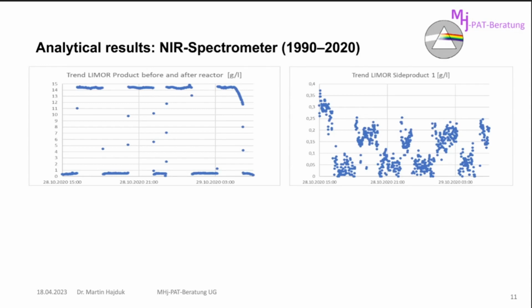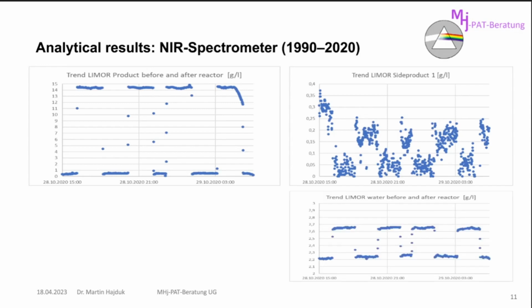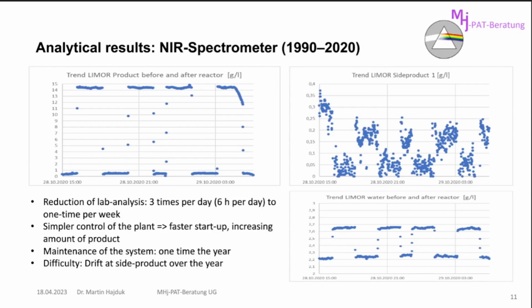You see, it's not so easy to measure the side product with this technology. We have a variation of about 0.05 grams per liter. But for NIR, 0.05 gram per liter is really, really good. This was a system developed in the 1980s. And here I show the trend of the water before and after the reactor. You also see, same as here, the switching of the sample points, but the measuring is very stable.